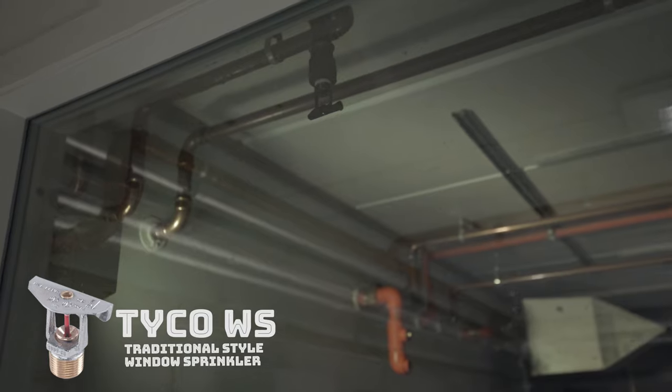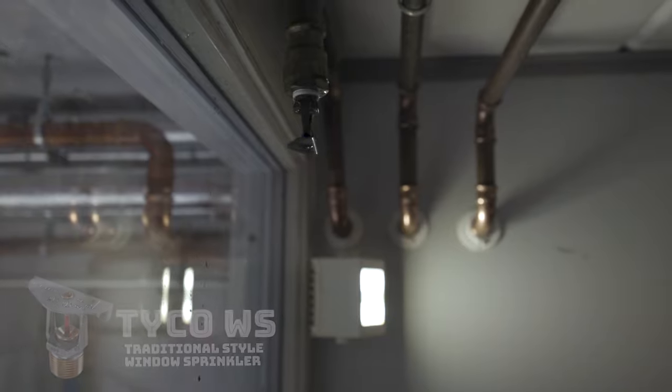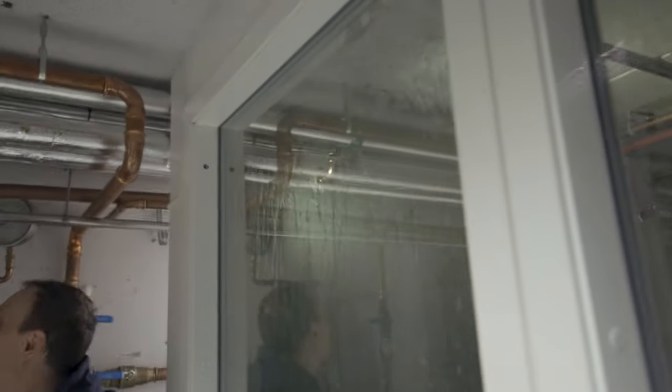The first sprinkler we were shown was the Tyco WS window sprinkler. This is a sprinkler head with a bulb that expands the vapor inside the bulb, which then explodes, letting water flow out the head and onto a plate. That plate guides the water in a spray towards the window, creating a film of water and protecting it with high fire resistance for about two hours.